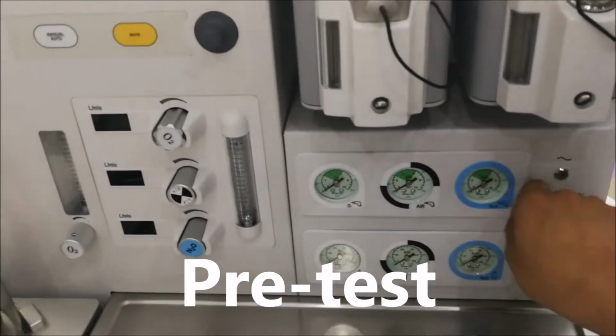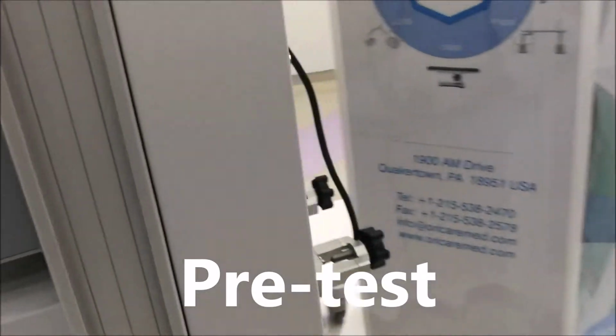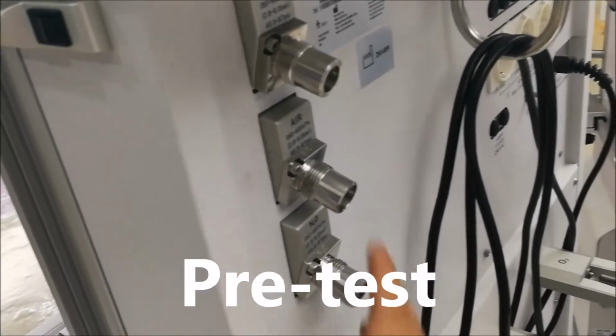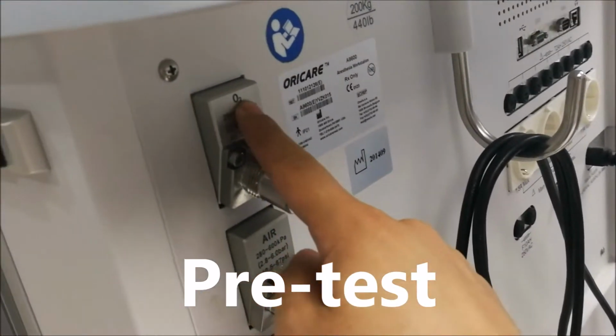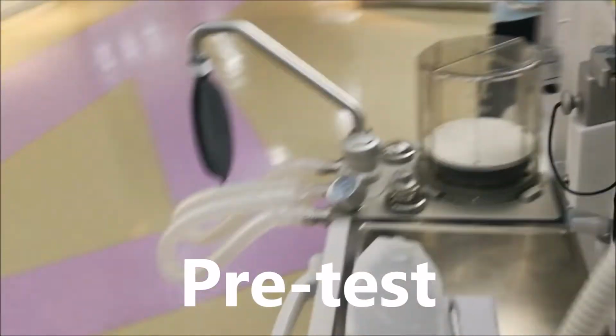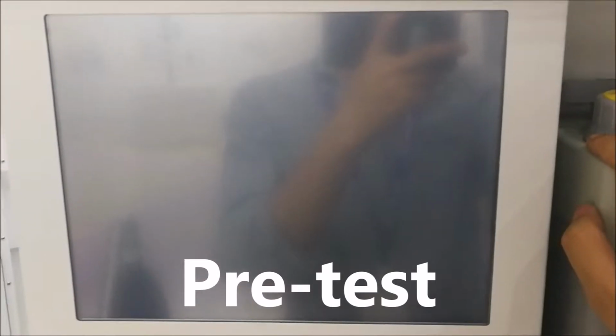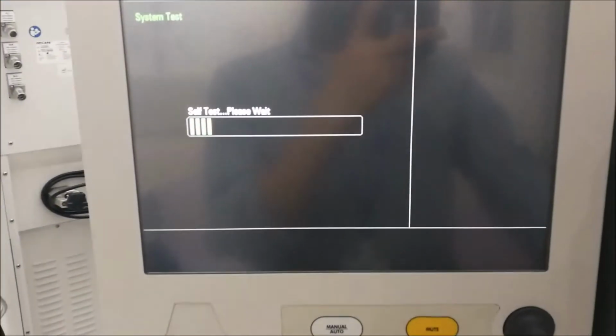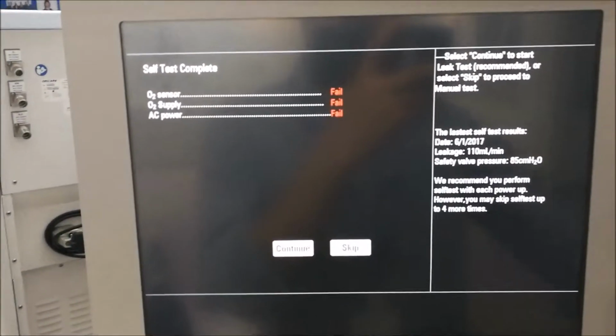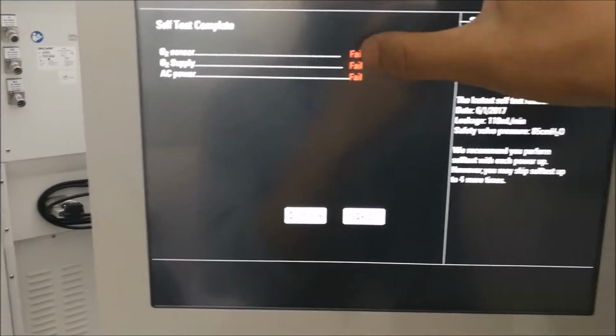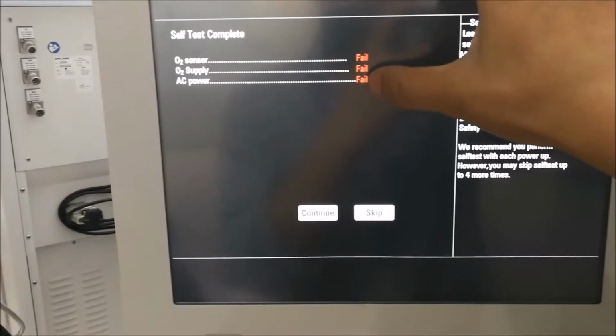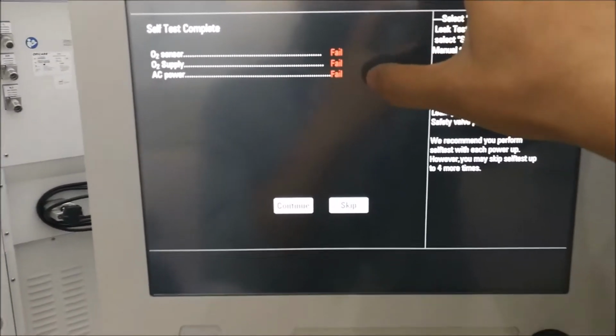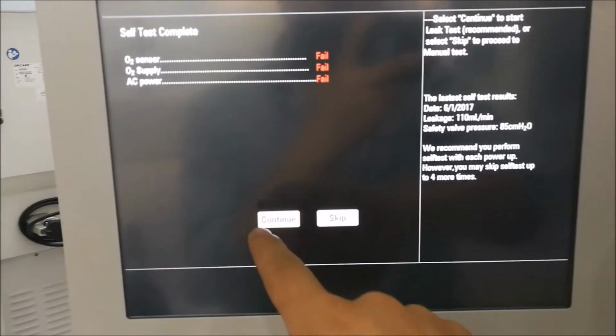Okay, first we need to turn on the machine. Before we turn on the machine, we need to connect the gas supply. We have 3 tubes to connect it. Different. Here will show you which one, oxygen, air, or nitrous oxide. Okay. When we turn on the machine, it has a self test. Wait a moment. Okay. Now it does the safety system test, and first it will test the oxygen sensor and the oxygen supply. If we connect the gas supply, it will be okay, and the AC power we connect to the power socket. Okay, now we haven't it, so we just skip. If you have, just continue. It will pass.